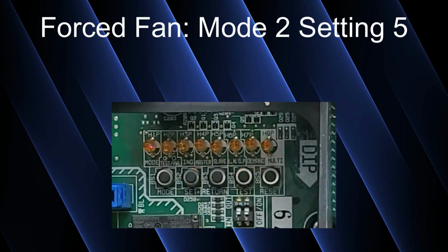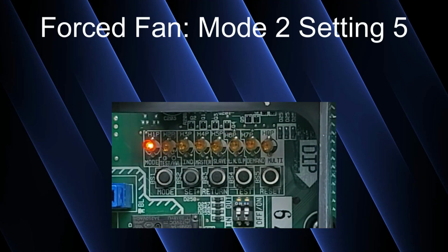Then press return. When you press return, it's going to show you the current option. Current option is off or disabled, which is H7P. So H7P will be sitting there flashing. Ignore H1P, it's still solid. That's just telling you what menu you're in. You're in the service mode menu, that's fine. H7P is flashing. We need to enable forced fan. So we press set 1 time to move it from option 1 to option 2. H6P has a binary value of 2.